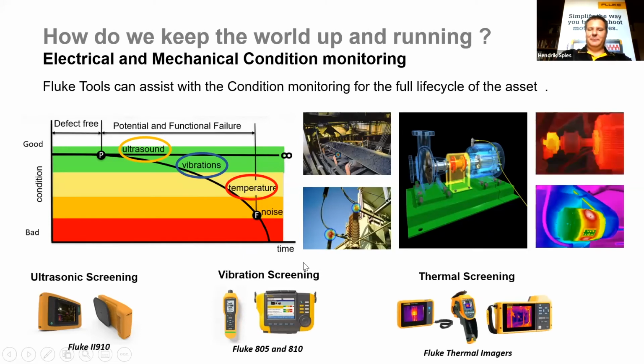Last but not least is temperature. So Fluke has got a comprehensive thermal imager range, starting from a low pocket thermal imager to a professional series and a tablet type professional series thermal imagers. So typically here we will look at mechanical, as you can see, a bearing, and we can look at problems on motors where maybe we can see some electrical problems, like this can maybe be a harmonic distortion coming from the supply, or this can be that the actual windings of this motor are starting to fail. Abnormal high temperature on this motor windings.